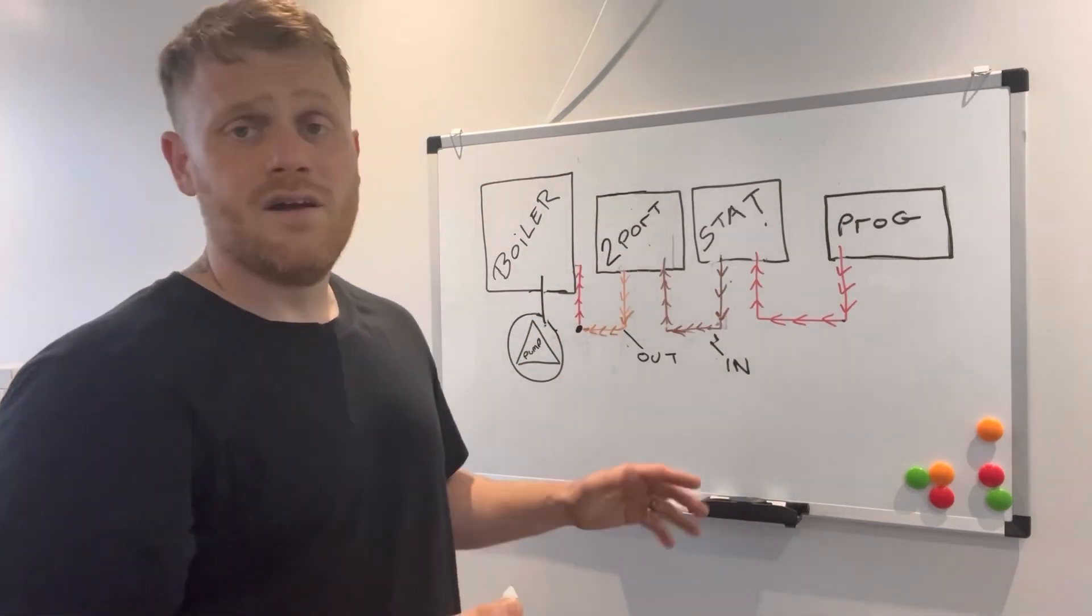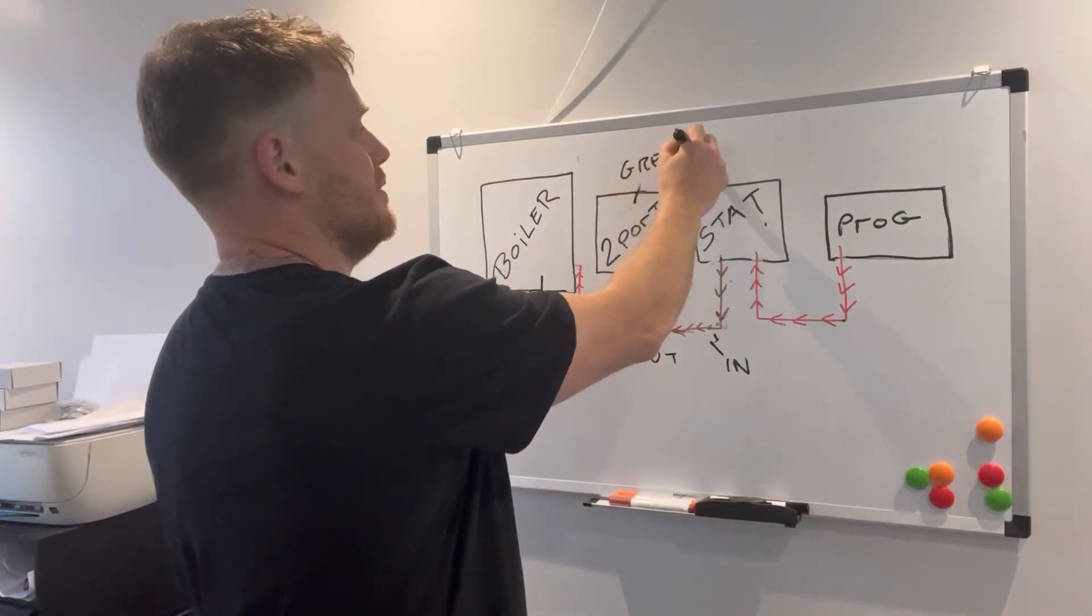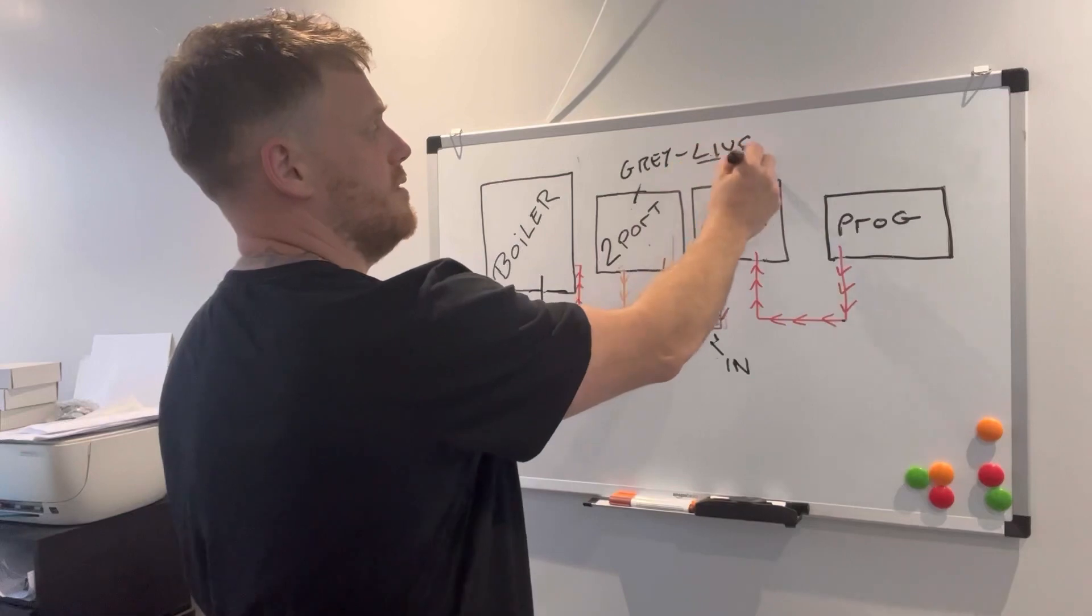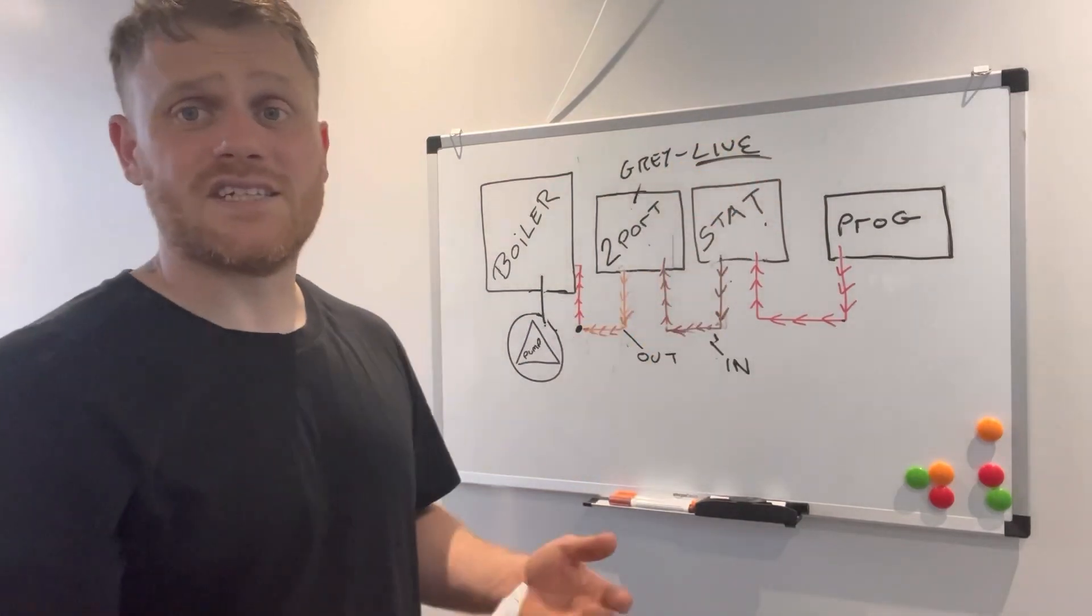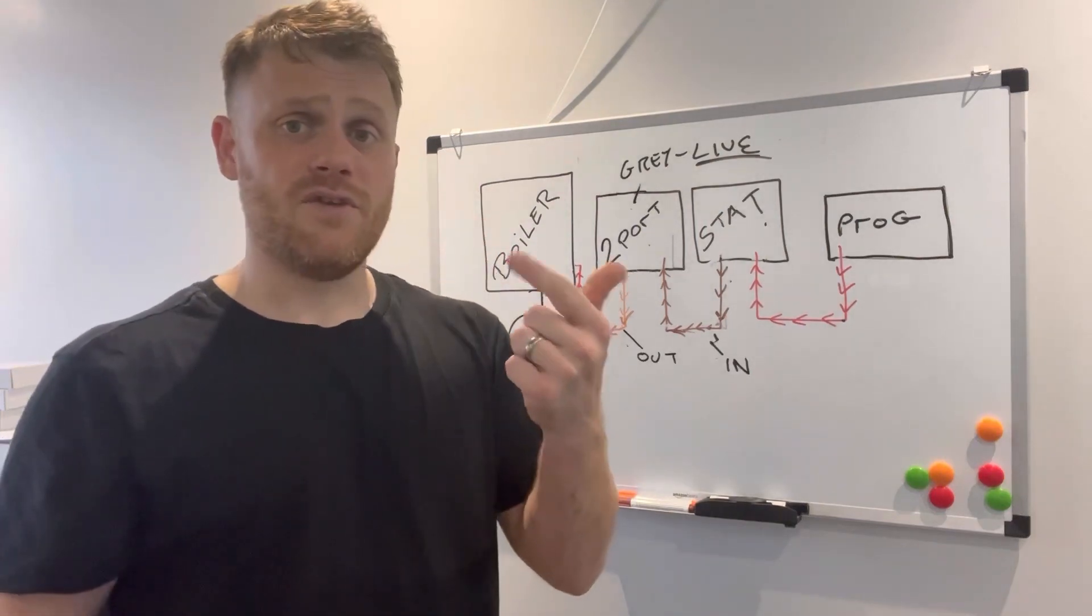The reason I say brown is in is it's your feed in after your programmer and your stat. It's what's going in to your two-port, and the orange is the power coming out. And the other wire which I haven't even mentioned is the gray wire. So the gray wire is the live, that's the live supply to the two-port.